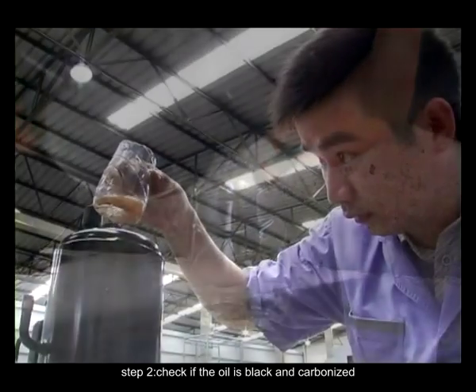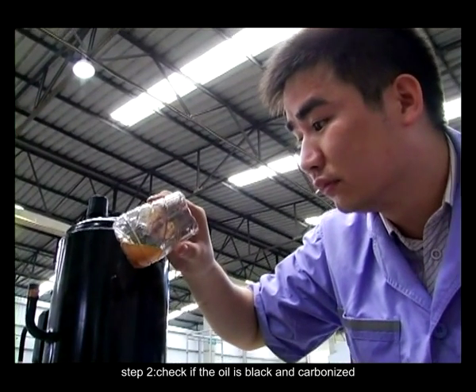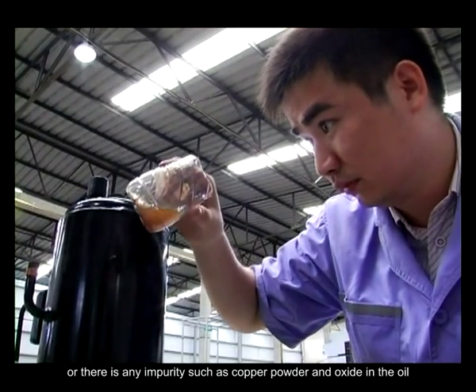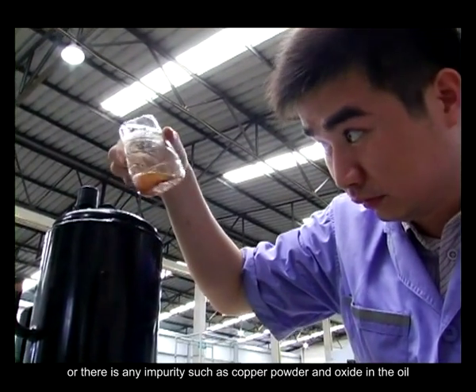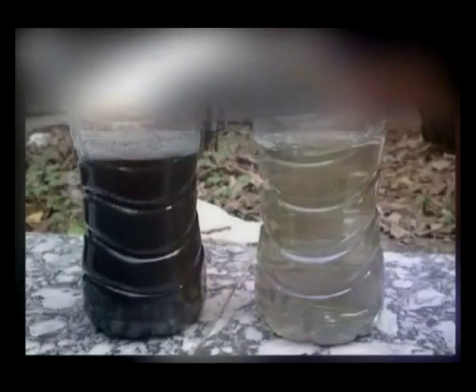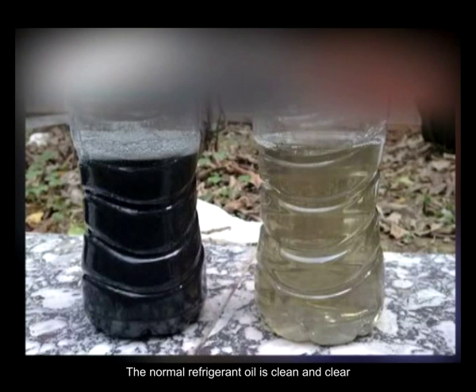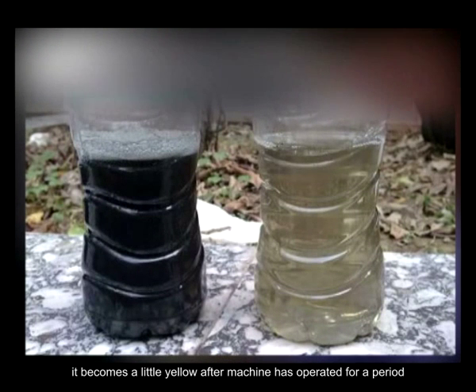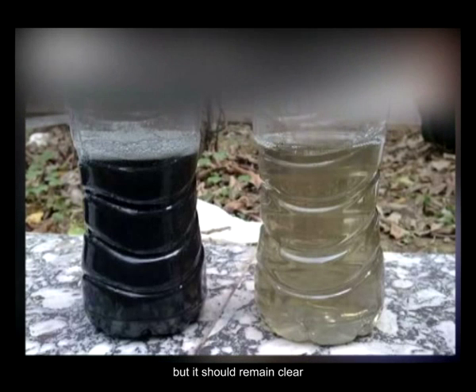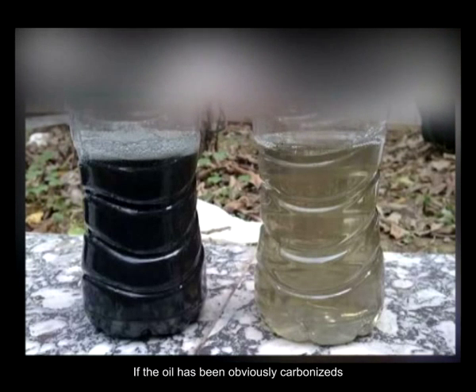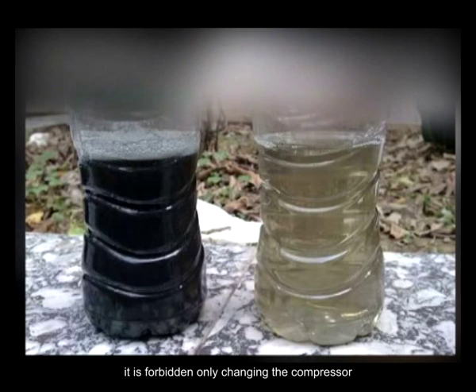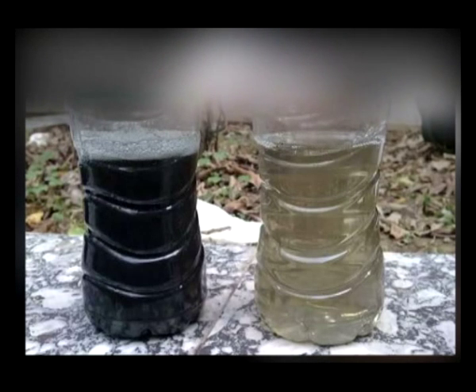Step 2. Check if the oil is black and carbonized, or if there is any impurity such as copper powder and oxide in the oil. The normal refrigerant oil is clear and clean. It becomes a little yellow after the machine has run for a period, but it should remain clear. If the oil has been obviously carbonized, it is forbidden to only change the compressor.